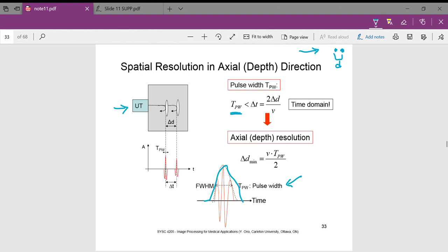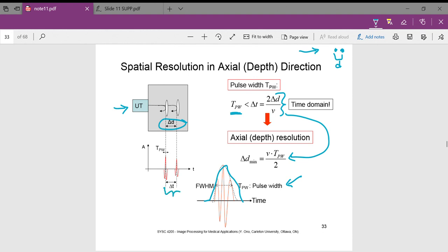The equation for TPW (pulse width) is given here. Our axial depth resolution is going to be the change in distance, so we rearrange this formula to get the axial resolution value. What we are looking for is this distance — and if we look at that in terms of amplitude versus time, it is this time value.